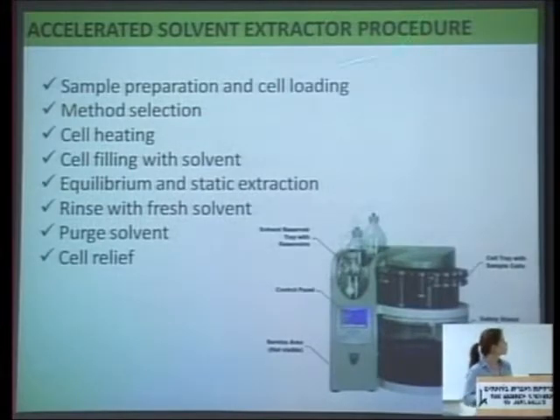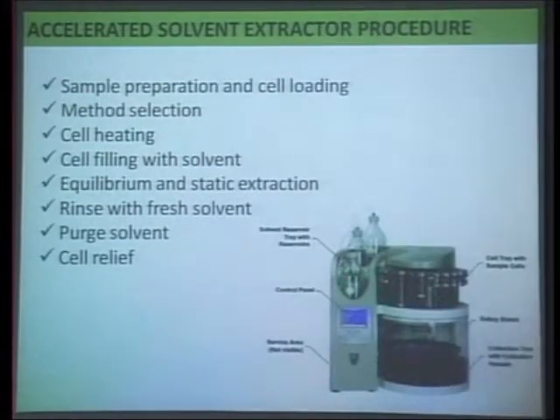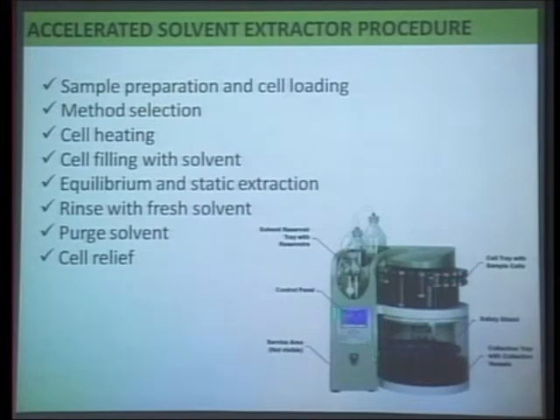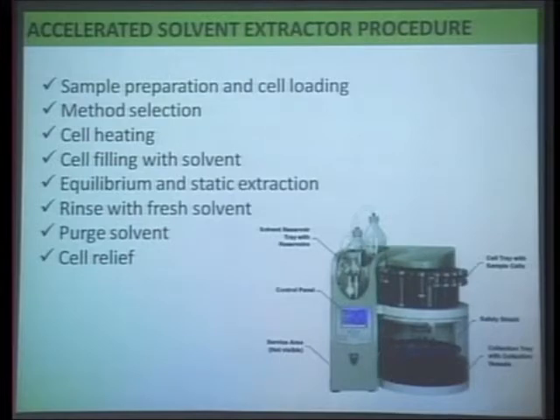This is the ASE — the accelerated solvent extractor. For the procedure, we load our sample in these vessels and select the method on the display. The cells go into the oven where they are heated to temperature equilibrium and extraction takes place. Then we collect the extract in glass vials for chemical analysis.